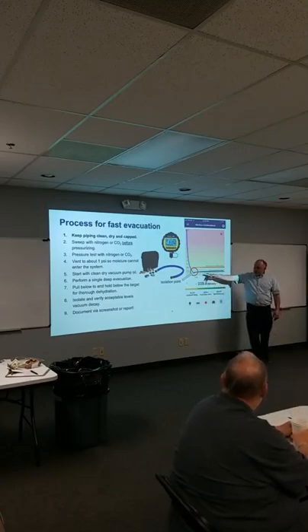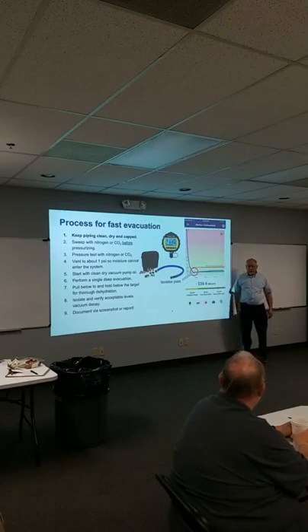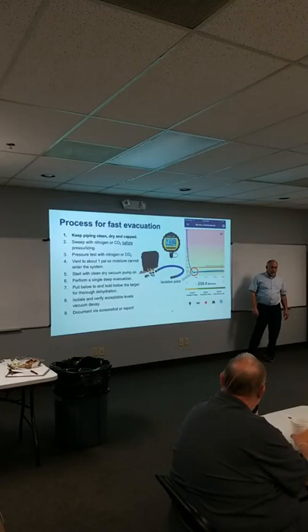You're gonna pull a single fast evacuation, so down, isolate. When I isolate it here, this is leveled off. This is 20 minutes later. It only went up to 239 microns. All right. If you buy an AccuTools vacuum gauge, it's going to drive you freaking crazy, because you're going to realize very quickly that it never ever stops rising.